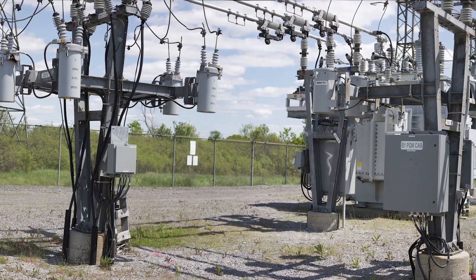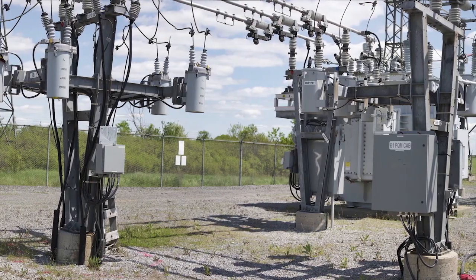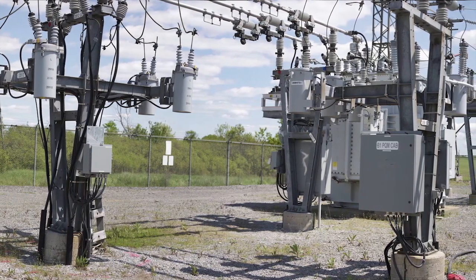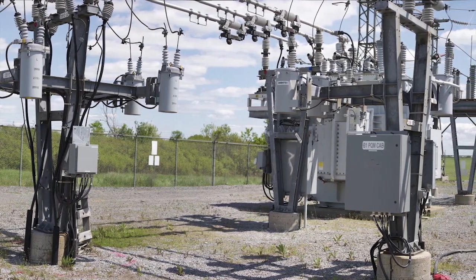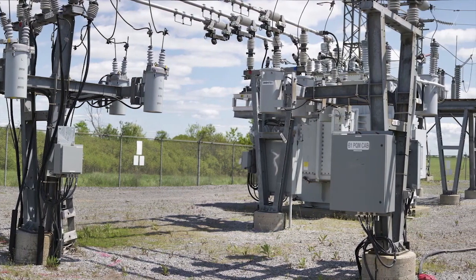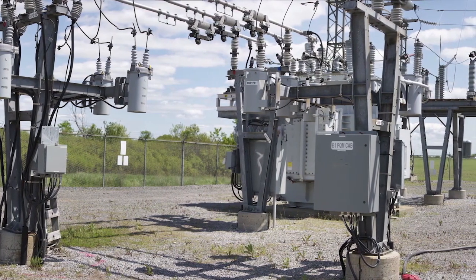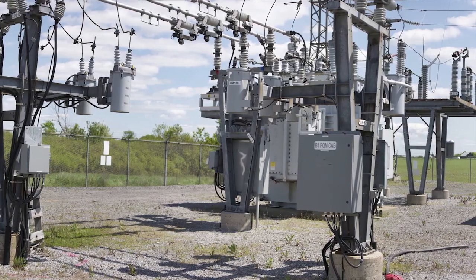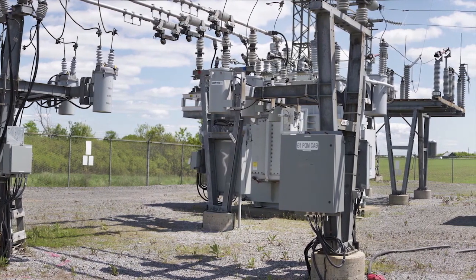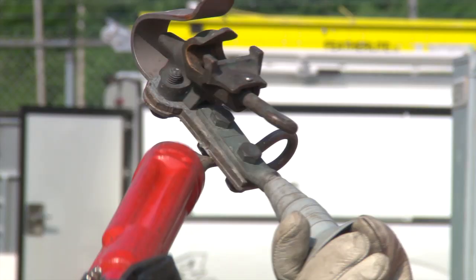Before connecting the cables to the DS feeders, inspect the bus and insulator for damage or missing components, and ensure workers have a clear path to exit the area in case of an event, such as a broken insulator, a stirrup malfunction, or cable failure. Connect the MUS neutral to the DS neutral, and then connect the low voltage cables to the appropriate DS feeder positions.